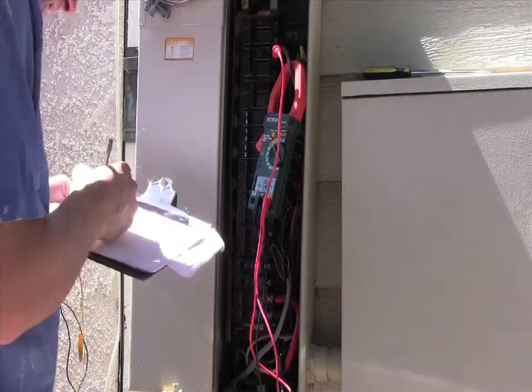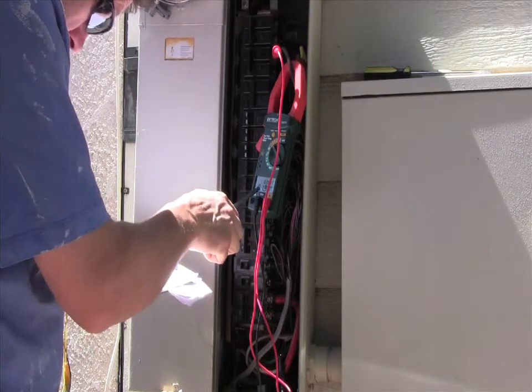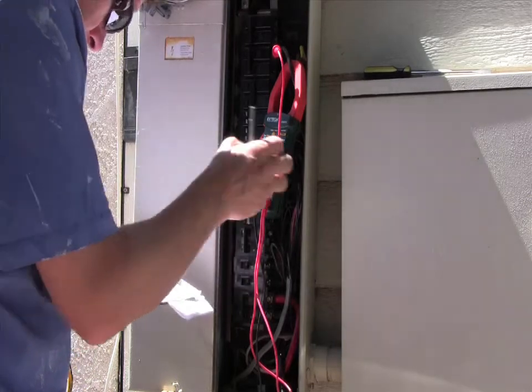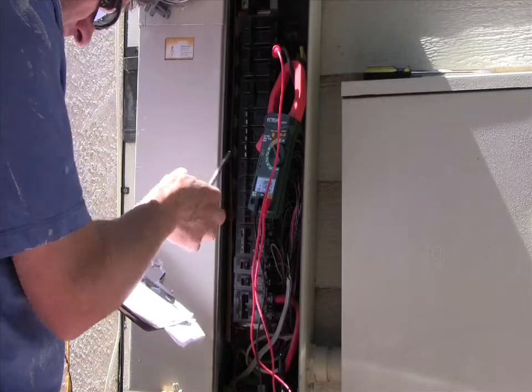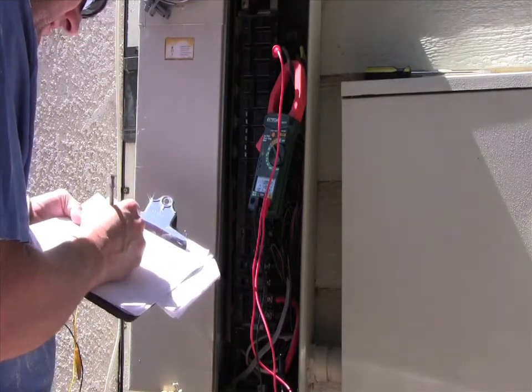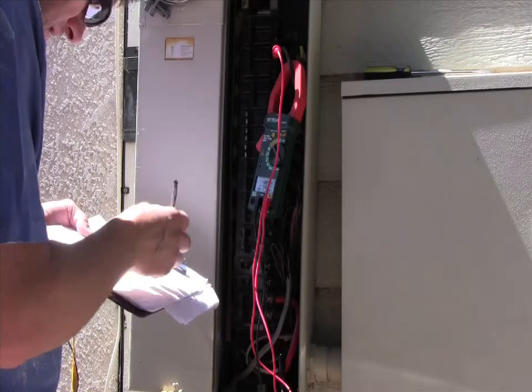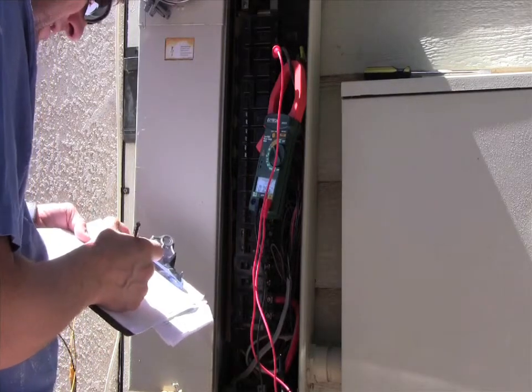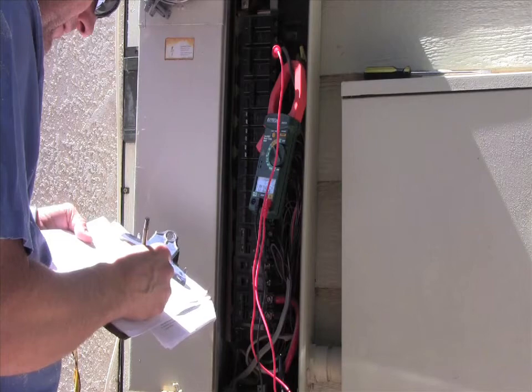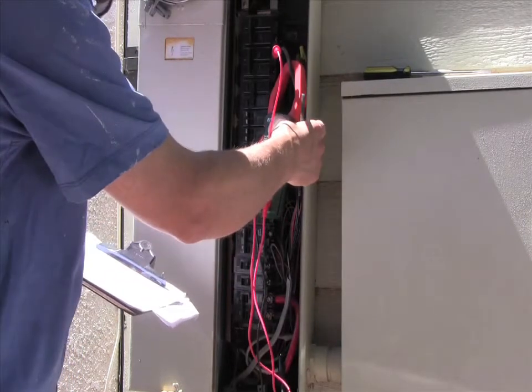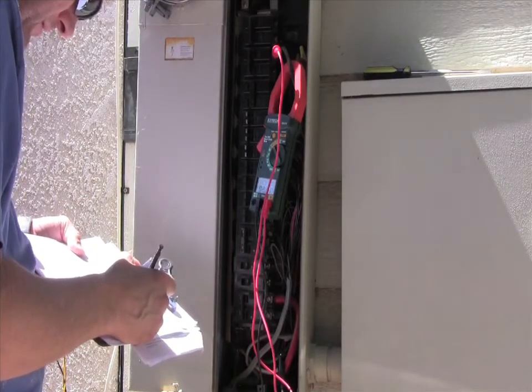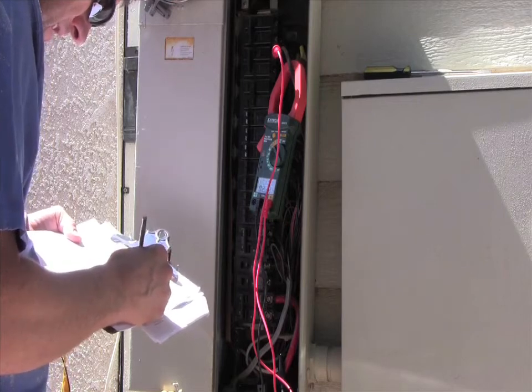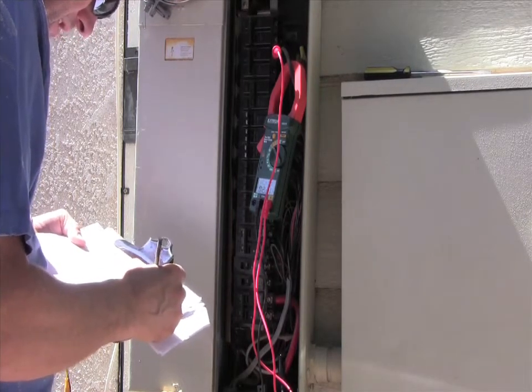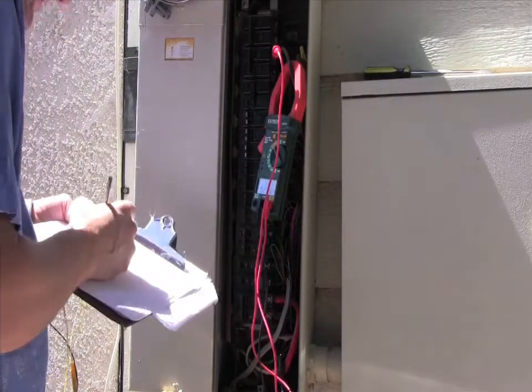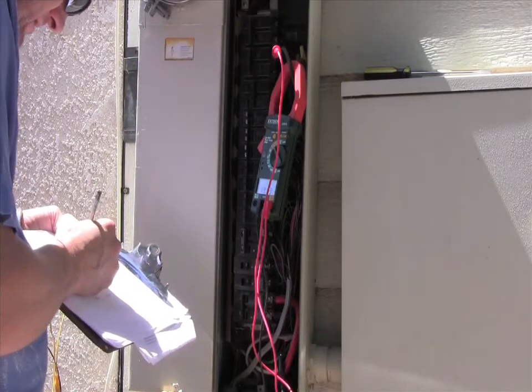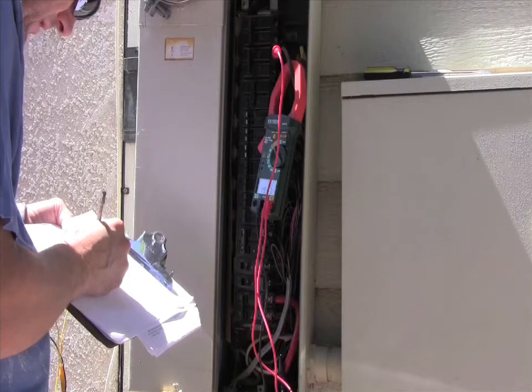We have 2.62 horsepower. And we're showing 1.94 kilowatts. We have a power factor of 0.858. It's lagging. We also have a 1.18 kVAR. We'll actually have our true degrees coming up here. So we have 31.1 degrees lag, and we're at 2.31 kVA. We're at 118.1 volts, running at 19.47 amps.